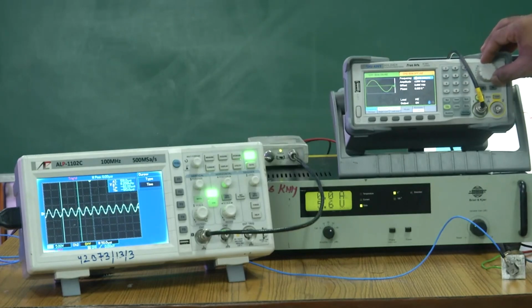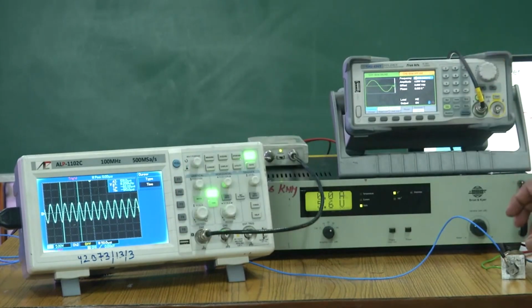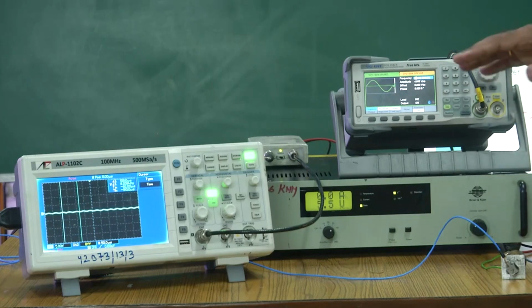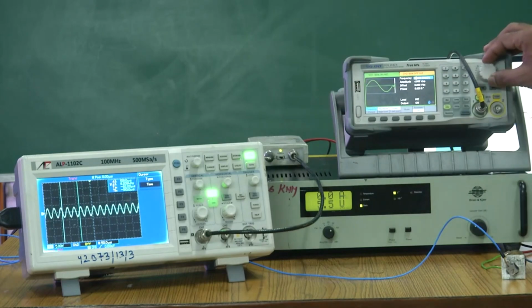then 21 and then 22, as you can see, the amplitudes are rising because the vibration of this sensor is closer to the natural frequency, and so we are approaching a resonance condition. So right now it is 22 kilohertz, and suddenly if I shift it from 22 to 23, the amplitude drops, which means that near 22 or 23 kilohertz I have one resonance which is definitely appearing here. If I increase it further, there is an increase in the amplitude of vibration.